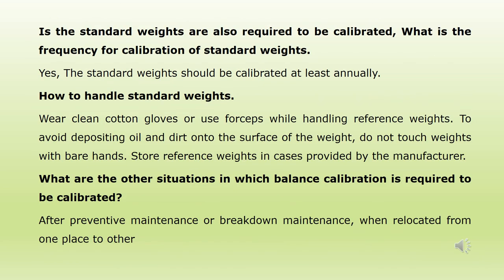Are standard weights also required to be calibrated? Yes, standard weights should be calibrated at least annually. How should standard weights be handled? Wear clean cotton gloves or use forceps while handling reference weights to avoid depositing oil and dirt onto their surface. Do not touch weights with bare hands. Store reference weights in the cases provided by the manufacturer.